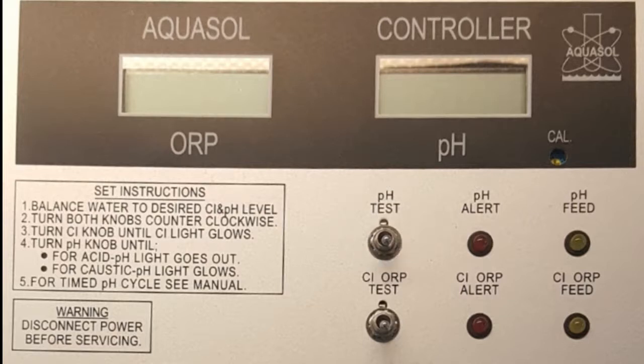Next, we have the CL/ORP test switch. This is also a spring-loaded switch that allows you to confirm that you're getting power to the CL/ORP feed system. If the CL/ORP alert or feed limit LEDs are lit, this switch will not operate. This switch will also not operate if dip switch number 4 is on, in the position and the pH LED is lit.